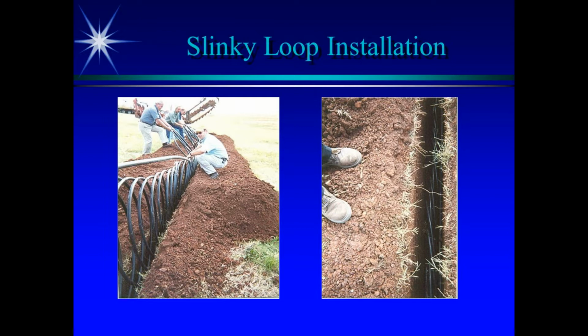Well, this is a way to get that pipe in the ground, get the BTUs out of there, and shorten up the loop, because now we're standing it on edge and looping things over each other. It's not as efficient as far as the amount of pipe, because at these cross sections you're losing some heat transfer, but you're making up for that with extra pipe. And pipe, in the whole scheme of things, is cheaper than the extra footage of land or the alternative we'll see next.